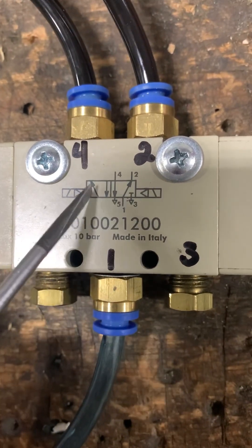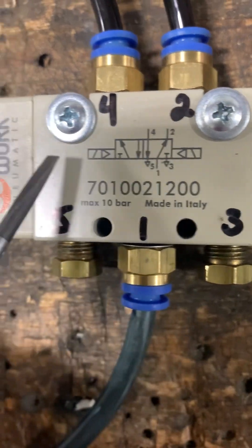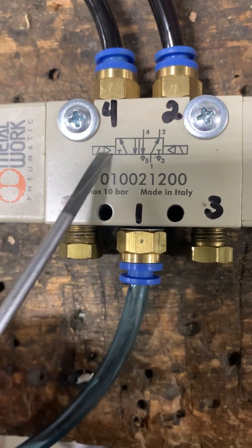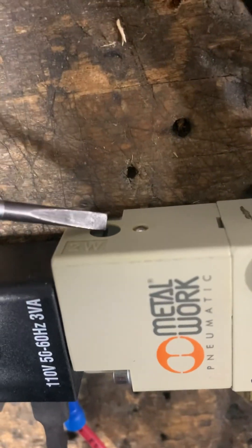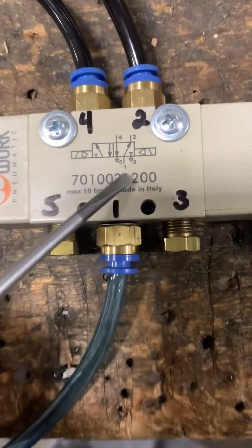These are coil-controlled on each side — 110-volt coils. On the pneumatic diagram of the directional control valve, you can see these symbols. This one is solenoid coil-controlled with a manual override, because it does have the override buttons. The position with the numbers is your normal starting position when the coils are not energized.